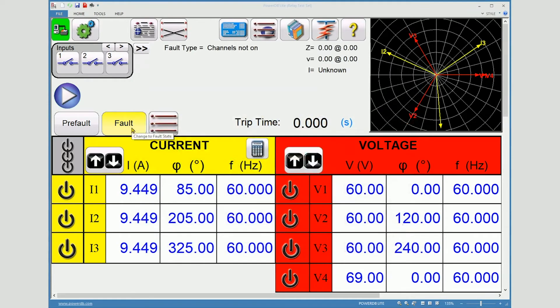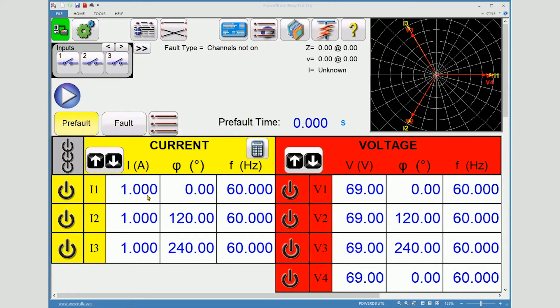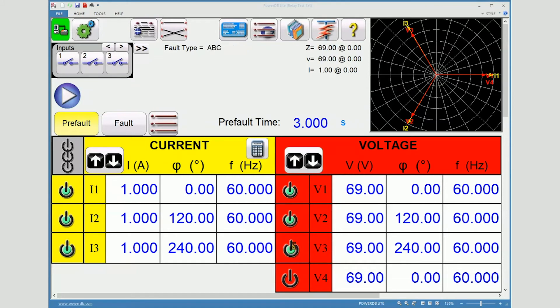6.35 ohms at 85 degrees. When I accept these values, the amplifiers will be configured for the test. Notice the fault values are now 9.4 amps at 60 volts. Pre-fault is 1 amp at nominal angles. I will set a pre-fault time of 3 seconds. Select each amplifier which is intended to come on. As I do, notice the fault type is displayed for me.